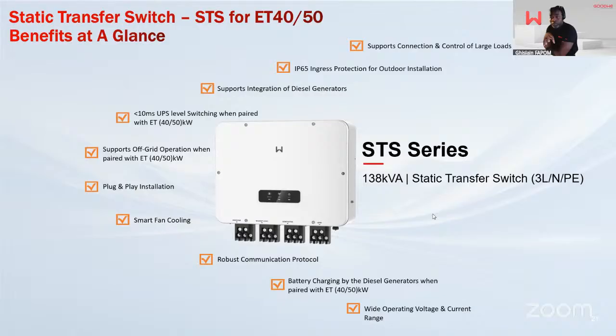So, IP65 for outdoor compatibility, integration to diesel generator, 10 milliseconds of switch as before. Support off-grid operation, can be paralleled off-grid, plug and play, smart cooling, robust communication protocol, and battery charging by the diesel generator when you have the STS box. So that's very important, because you need the diesel generator to basically be able to complement the grid when the grid has fallen.